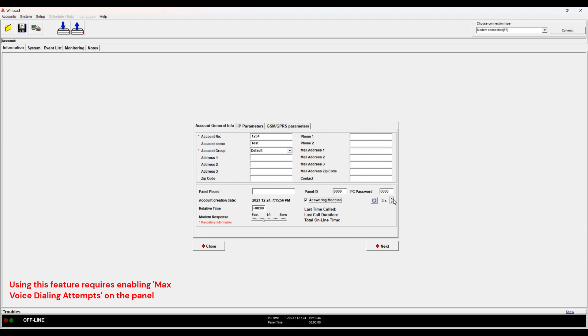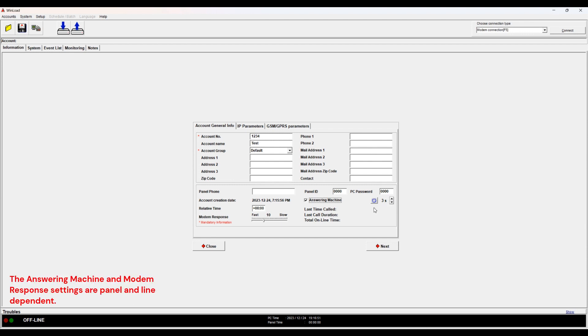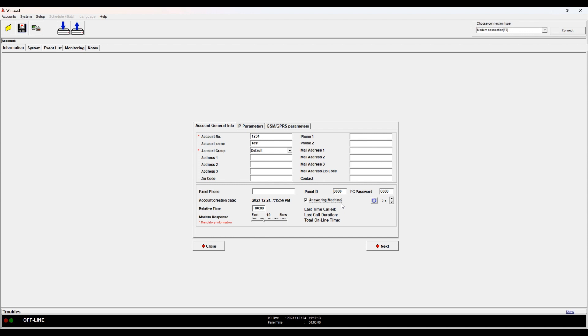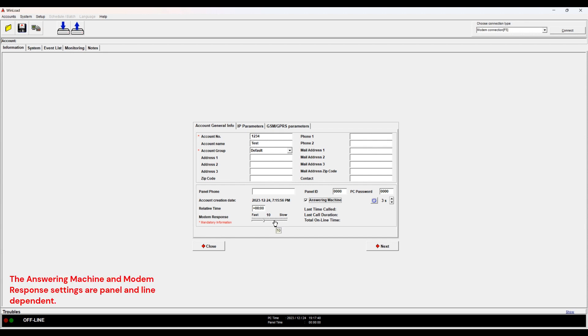For the phone line, you would click on answering machine and then you would set this to three or maybe six, it's up to you. You have to try. Of course, with some commercial sites they have a fax machine and the fax machine is set up to answer right away after the first ring. So if that's the case, unfortunately the only way to log in is to ask them to disconnect the fax machine until you are done. Otherwise, if they have an answering machine or even if it's a fax machine that is set up to answer after three rings, then when you enable this option it will dial once, it will hang up right away as soon as the phone starts to ring, it will disconnect and then dial again. So on the next dial, the alarm panel will pick up right away because it's expecting that someone is trying to dial into it. This modem response option...